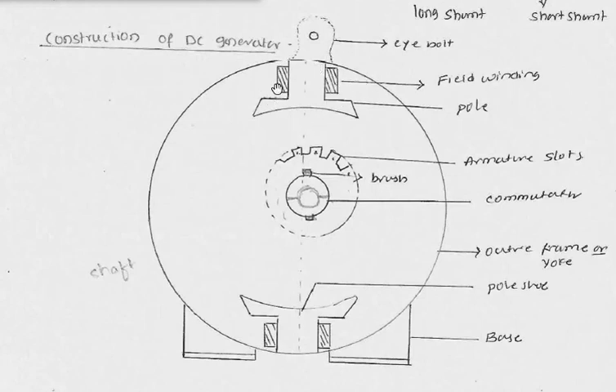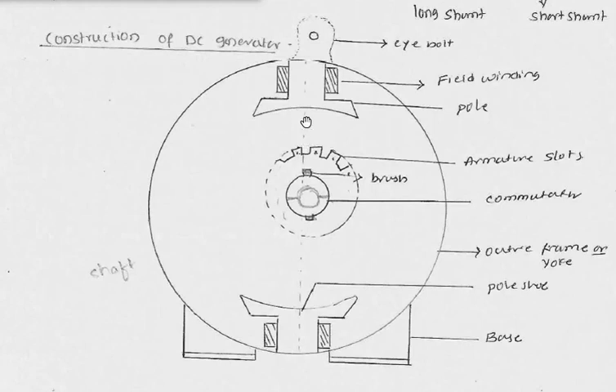In the main pole, we have a pole core and a pole shoe, and on the pole core we have the field winding. The pole is bolted onto the frame as a stationary part, with the field winding on top of it. The field winding creates the magnetic field. The air gap shown in the diagram is actually very small — about 4 mm or 6 mm.